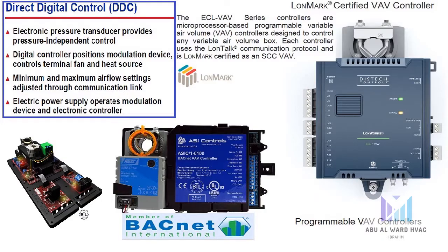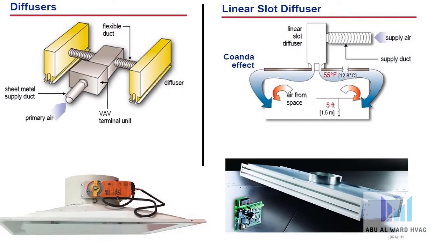The next important component of VAV terminals is diffusers. Each VAV terminal unit is commonly connected to a downstream sheet metal duct that is then connected to remotely located diffusers by flexible ducts. Diffusers distribute the supply air effectively to the conditioned space. Proper air diffusion is an important comfort consideration, especially in VAV systems, because VAV systems require the diffuser to provide proper space air mixing over a wide range of airflows. Diffusers specifically intended for VAV applications should be used to prevent cold air dumping at low airflow rates.